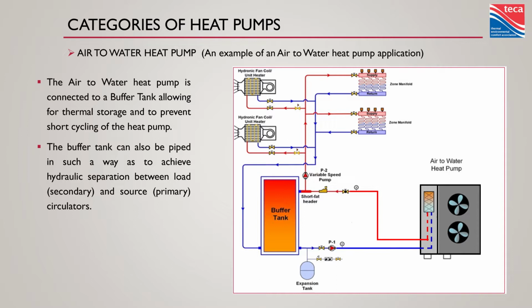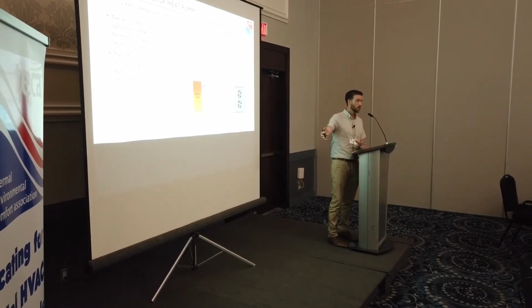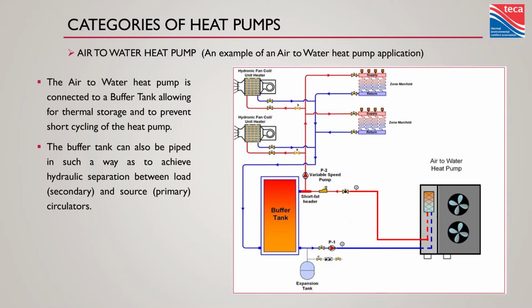So there's a few different ways to pipe a buffer tank that are pretty important. So this is a 3-port buffer tank configuration where we have our heat source transferring heat into the buffer tank and taking heat from the buffer tank, or fluid from the buffer tank to be reheated. We keep the hottest water at the top, coolest water on the bottom, because that's where they want to hang out. Buoyancy, it's a thing, we can't fight it. Keeps those hot air balloon guys up in the sky, they love their jobs. But on the load side, we're actually taking the water right off that supply of the heat pump before it touches that buffer tank. That's important for low mass heat emitters.